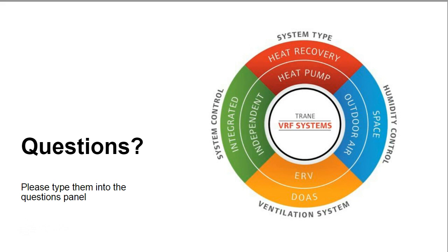All right, the next question is, can VRF system proprietary controls communicate via BACnet to base building DDC? We always have integration challenges. So this is a good question. Typically out of the box, and when I mean out of the box, I mean right from the factory with standalone controls, there really isn't going to be a method to communicate the controls via BACnet. In order to provide BACnet controls, your VRF system manufacturer will need to give you either a BACnet access license or provide a central controller that does have BACnet enabled on it.